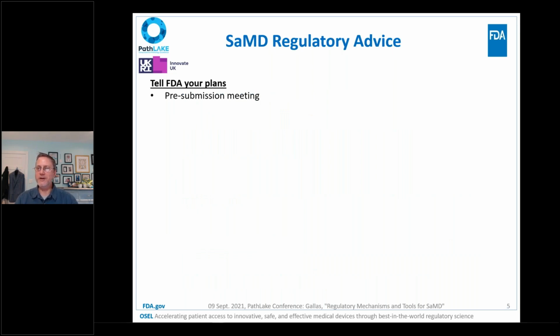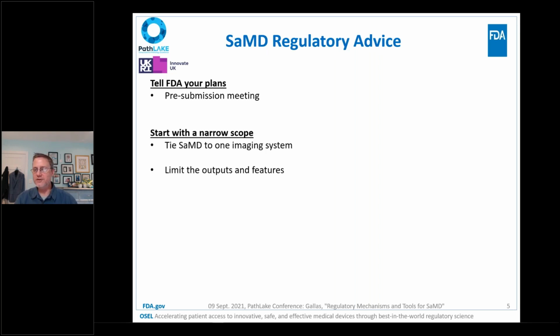So my regulatory advice is always talk to the FDA early. We have a program that allows us to hear about pre-submissions. And so please search online for pre-submission meetings at the FDA. That's the best way to tell the FDA your plans.